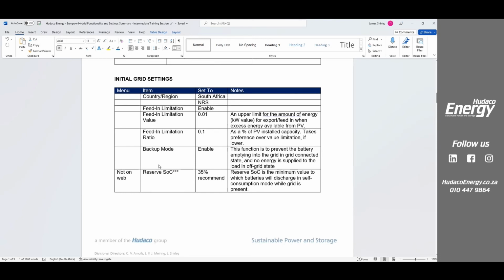We then have backup mode. So we click enable backup mode. And the moment we enable backup mode, that basically tells the system, because it's a true hybrid, you can actually install it without batteries. But because it's a true hybrid, as soon as you say backup mode, it says, okay, start using the batteries. Recognize and realize that there are batteries there.